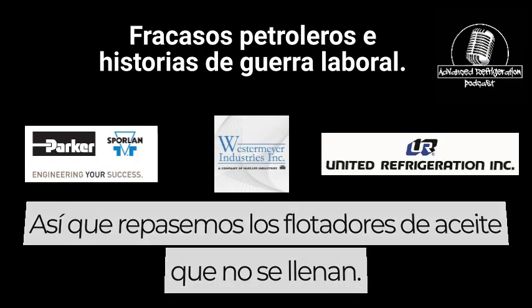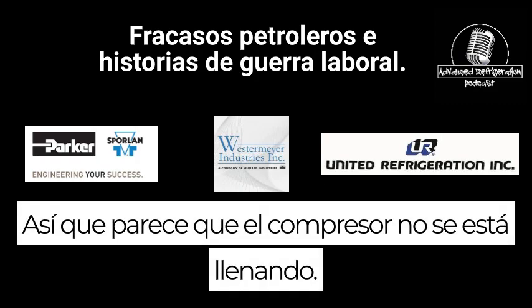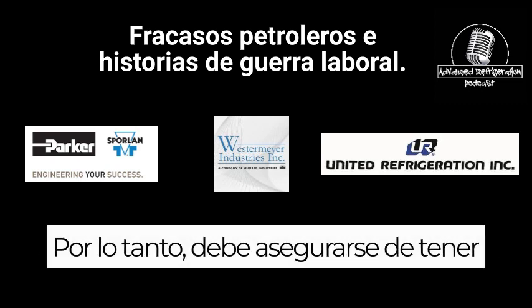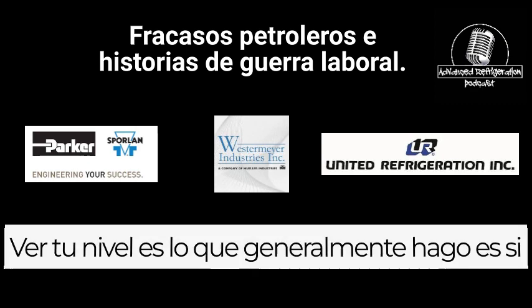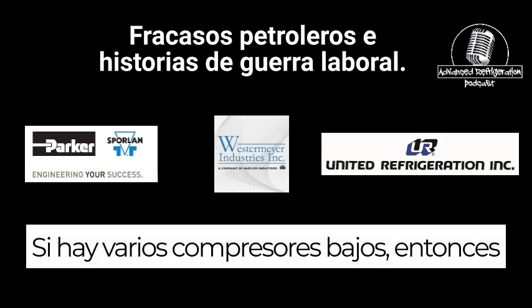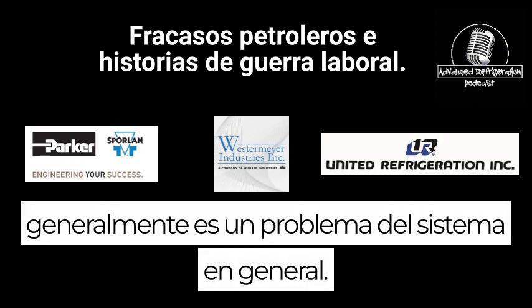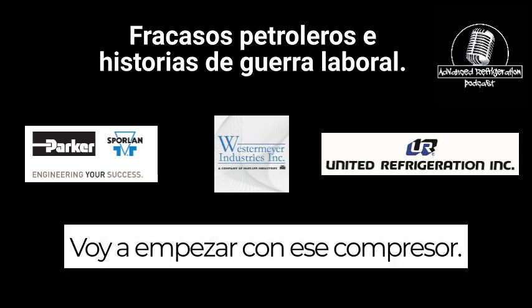Great. So let's go over oil floats not filling, or compressors not filling. It's another big one. First and foremost, look at your compressor and see what your level is. What I generally do is if it's one compressor, it's usually related to that compressor. If it's multiple compressors low, then it's usually a system issue. So if it's one compressor, I'll start with that compressor.